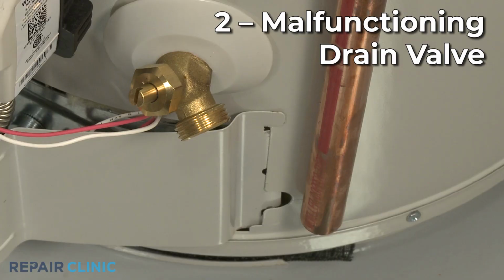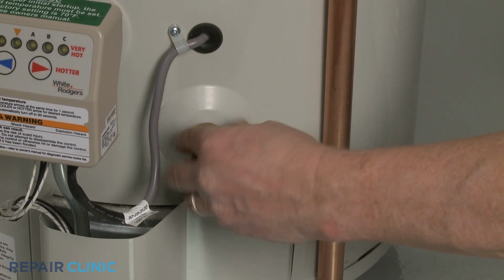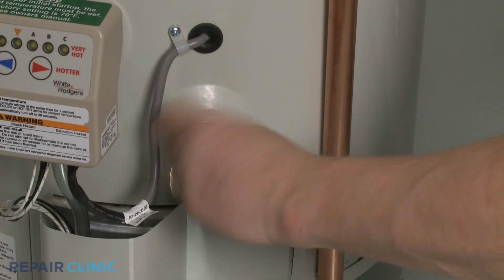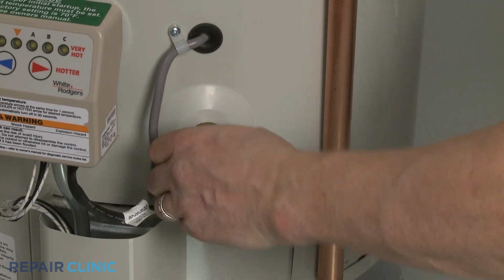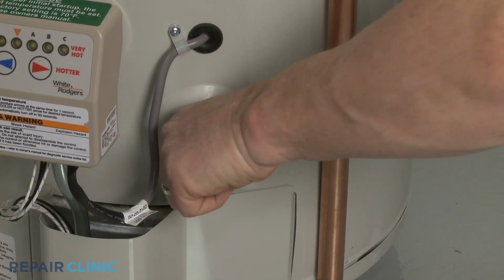The drain valve can be opened to drain the water heater for maintenance or to flush out mineral deposits that can collect in the bottom of the tank. A malfunctioning drain valve may develop a leak. Fully drain the tank and install a new valve to solve the problem.